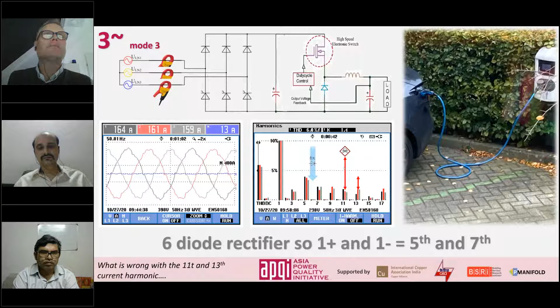What I was still wondering about is, what is this? The 11th and the 13th harmonic are jumping up and down, and it is even jumping so hard that it's going out of the reach of my analyzer. So let's investigate that. Normally I would use a Fluke current clamp, but when you're looking at the power quality in depth, you will need a high frequency Hall-effect current clamp, or just a shunt.